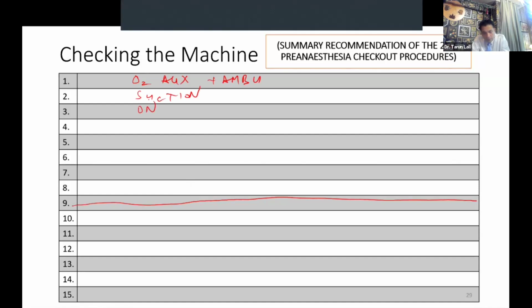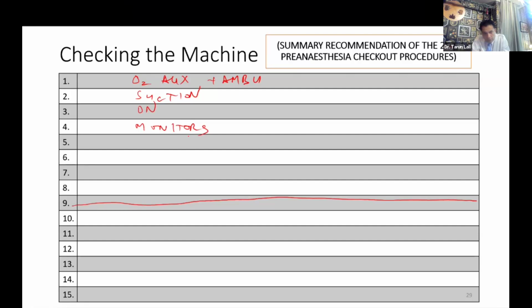And as I've turned the machine on, what also attracts my attention is that the monitors come on. So at the same time, I check all the monitors, whether all the settings are as per the patient that I'm going to take, and all the alarms are working or not. There is no additional alarm, but none of the critical alarms is muted. So after this, we come to checking the high pressure, intermediate pressure, and low pressure system.